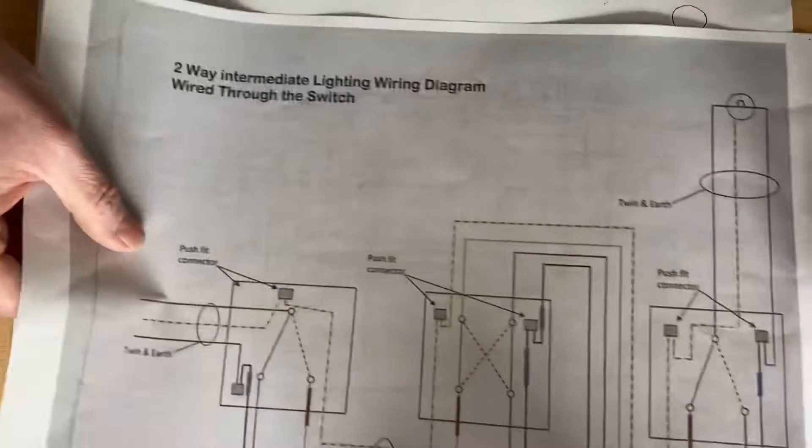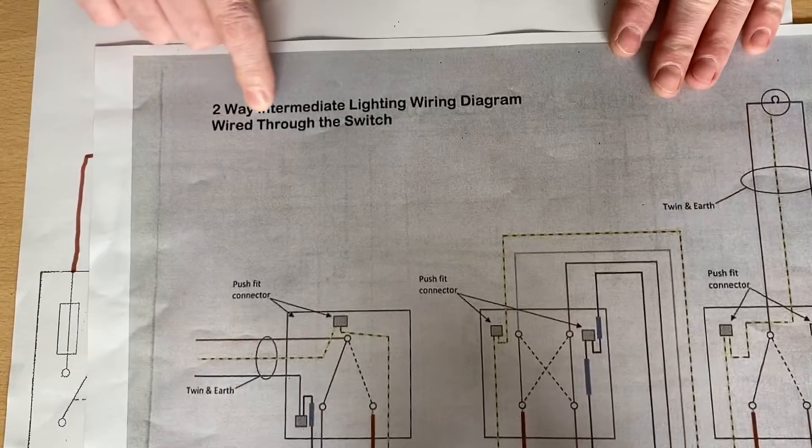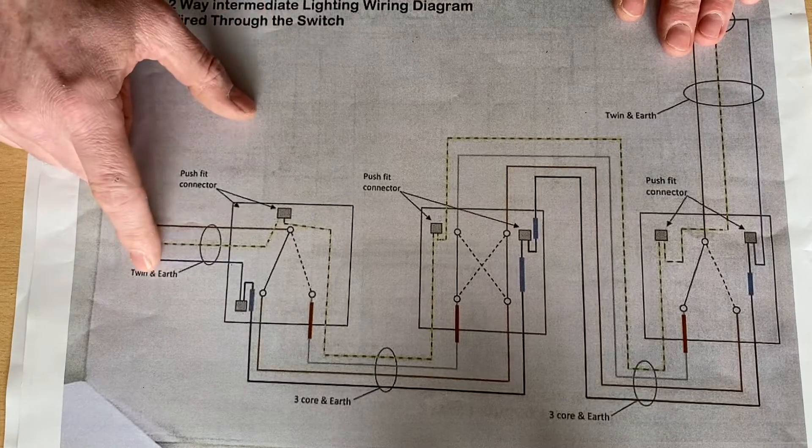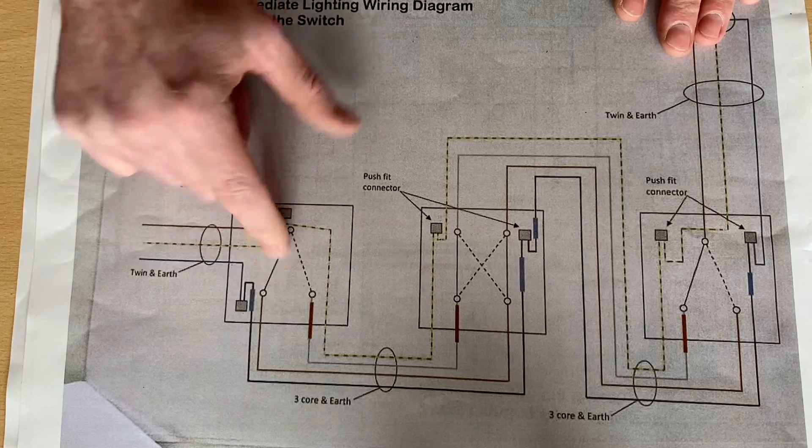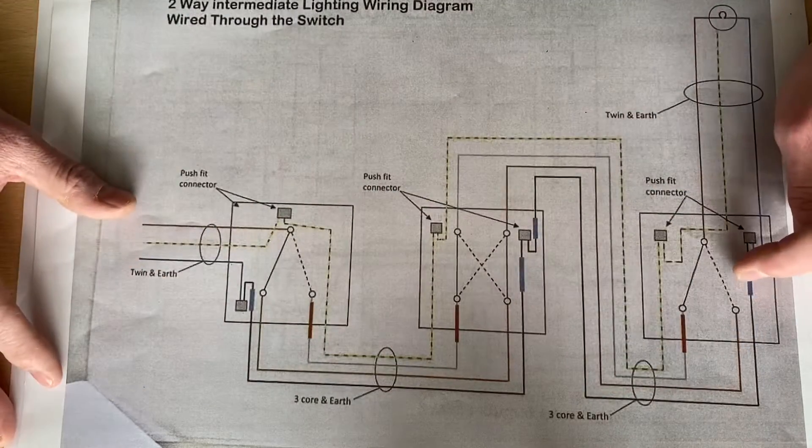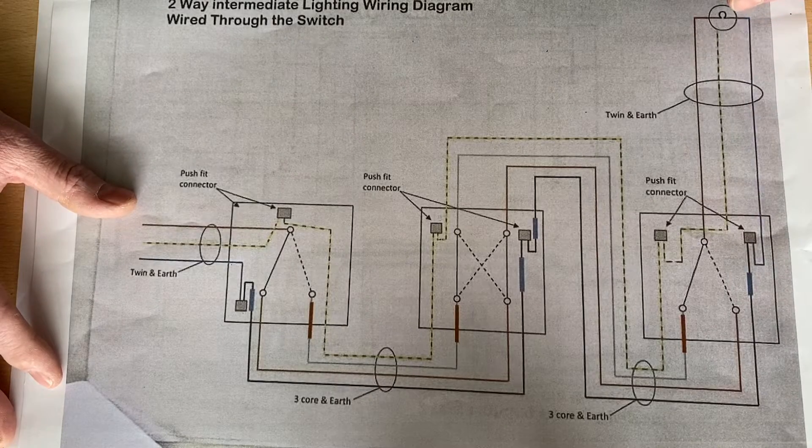This one just here, which was called wired through the switch. He brought the supply into the first two-way switch, brought a three core across to the intermediate, a three core across to the last two-way switch, and then a cable up to the lighting point itself.